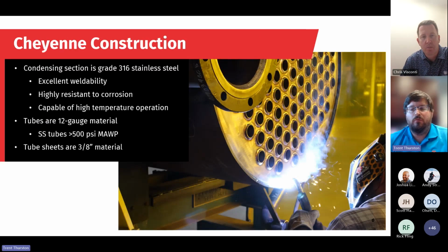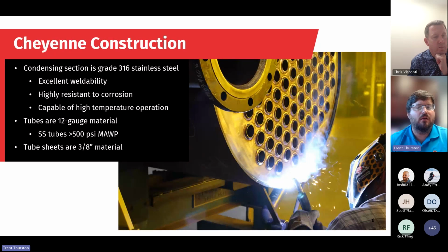So with the corrosive aspect of this, all parts of the condensing section are made of 316 stainless steel. So this is a very good corrosion-resistant steel. One thing we really like about it is it's very weldable. You can get a very good job welding. That's going to come up important in this next slide. And also it can deal with high temperatures. So we will eventually get down to a very cold temperature, but part of this will see a hot gas, and some stainless steels become brittle when the temperature rises over 570 degrees. 316 is capable of higher temperature operation. We do have much thicker tubes and tube sheets than the ASME code requires. And the reason for this is, again, to get a good weld, so we have this material to weld on and give us a good weld.